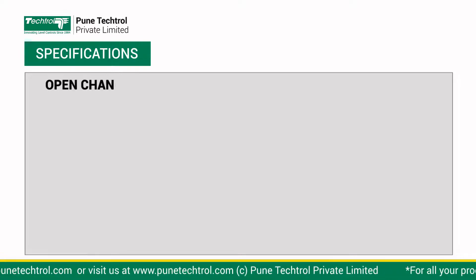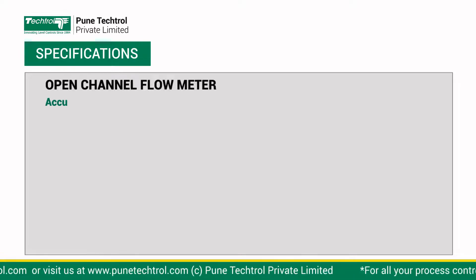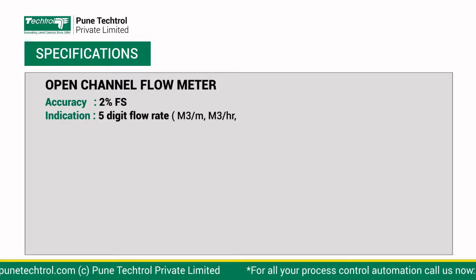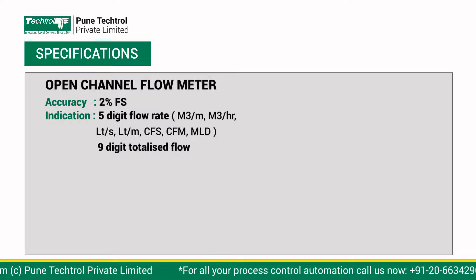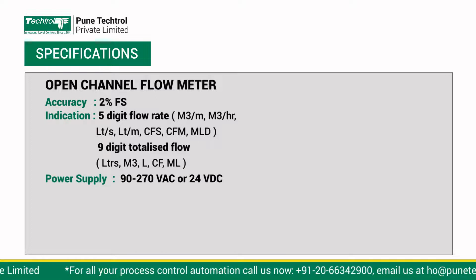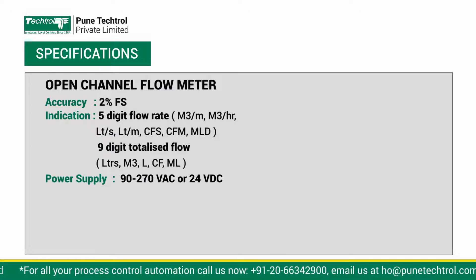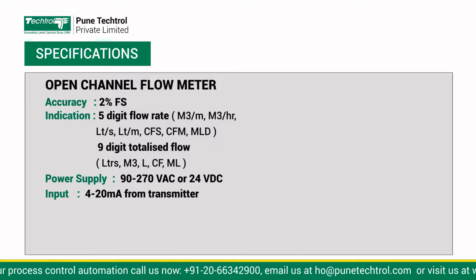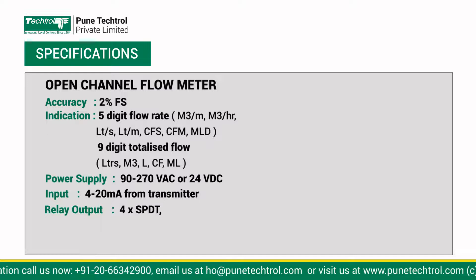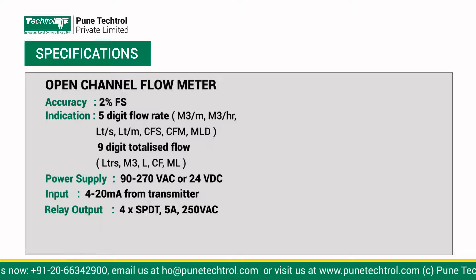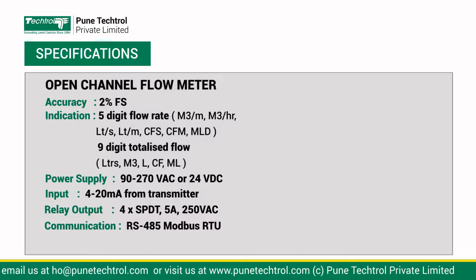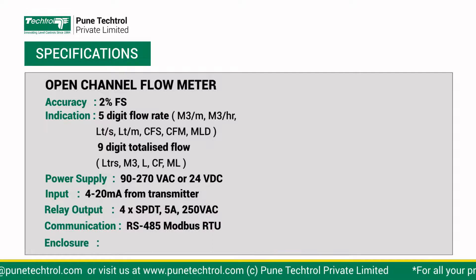Specifications for the open channel flow meter: 5-digit flow rate and 9-digit totalized flow in various units. Power supply: 90 to 270V AC or 24V DC. Input: 4 to 20mA from transmitter. Relay output: 4 SPDT, 5A, 250V AC. Communication: RS485 Modbus RTU. Enclosure: panel mounted.